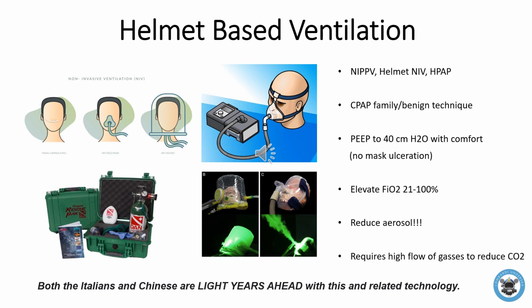The disadvantage to the helmets, and we'll talk about this in more detail in a few slides, but the significant disadvantage is that they require a high flow of gases to keep carbon dioxide levels down. So we need to continually flush out the space with fresh gas such that the patient's exhalations are not reintroduced as inhalations, and we have a buildup of carbon dioxide. But all in all, this was fascinating to learn about helmet-based ventilation. It certainly showed some promise and seemed like an incredibly viable path to reconsider these CPAP non-invasive respiratory therapies instead of just rushing to intubate the patient.